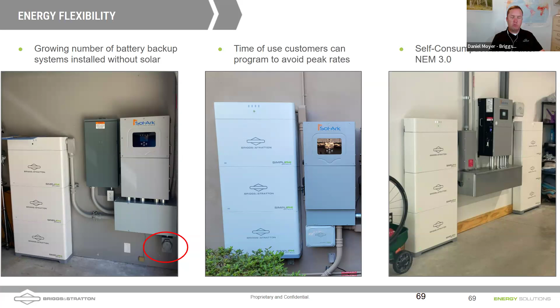If the grid's available, we're not going to close both relays simultaneously. We can never bring in the generator with the grid at the same time. So grid has to be unavailable to bring in generator power to charge the batteries. You wouldn't be able to accept two AC sources simultaneously to get multiple power sources to charge your batteries. You can use the Gen Force button to automatically start the generator as well. Reach out to Andrew and I if you want more context on that.